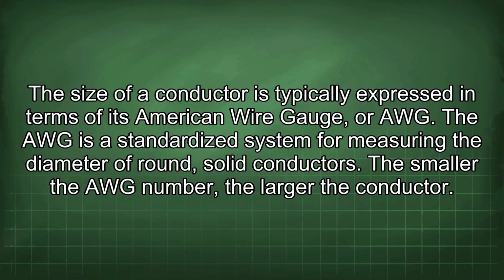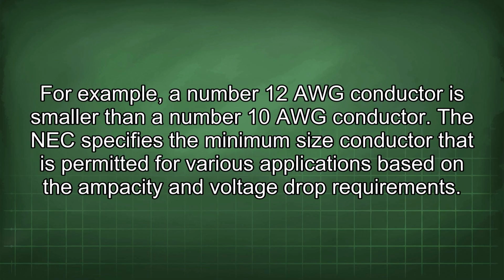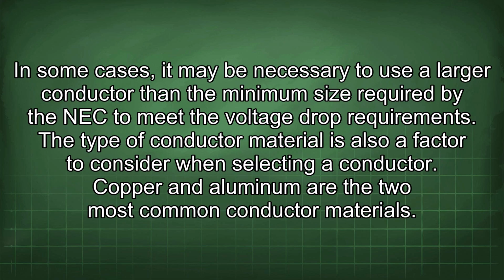The size of a conductor is typically expressed in terms of its American wire gauge, or AWG. The AWG is a standardized system for measuring the diameter of round, solid conductors. The smaller the AWG number, the larger the conductor. For example, a number 12 AWG conductor is smaller than a number 10 AWG conductor. The NEC specifies the minimum size conductor that is permitted for various applications based on the ampacity and voltage drop requirements. In some cases, it may be necessary to use a larger conductor than the minimum size required by the NEC to meet the voltage drop requirements.